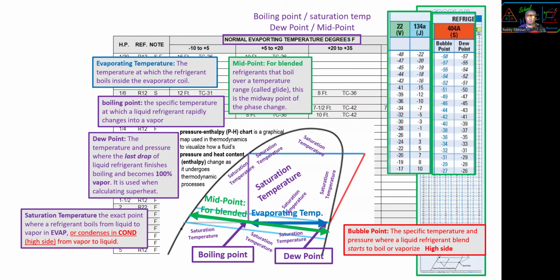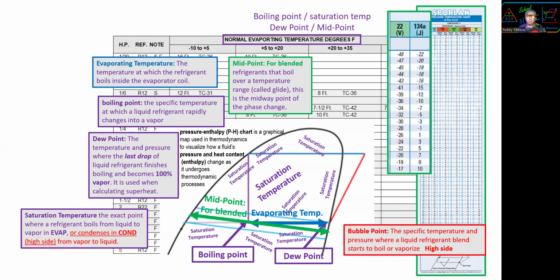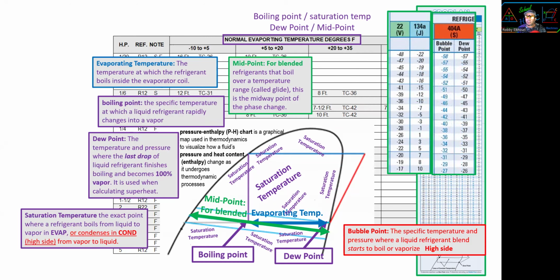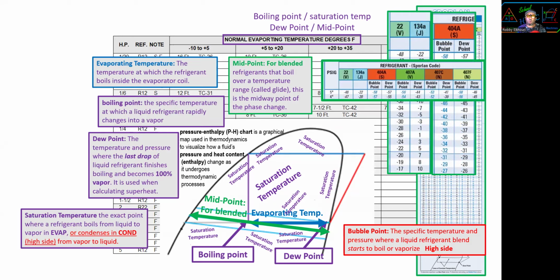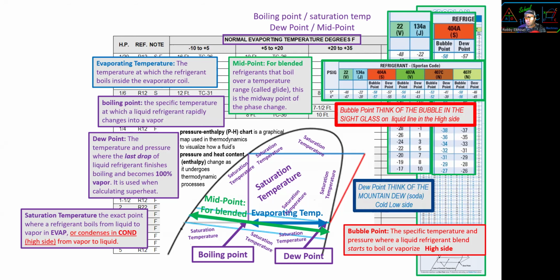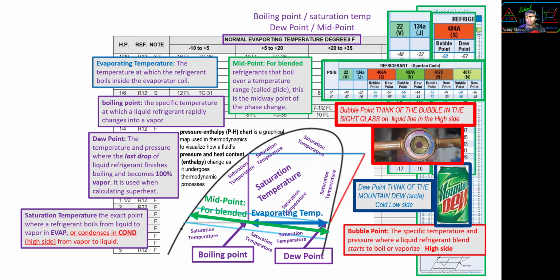So now we're going to go to the PT chart. We have pure refrigerant, non-blend, R22 and 134A. And we have, for example, R404, which is a blend. That's why you see bubble and dew. You see bubble and dew for the blends. Now, the bubble, think of the bubble in the sight glass on a liquid line of the high side. And the dew, think of the Mountain Dew soda, cold, low side. Bubble is high side, and soda, Mountain Dew, low side. That's how we know bubble and dew, easy to remember.